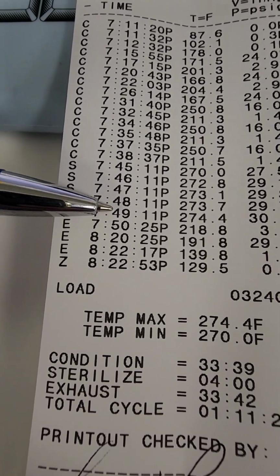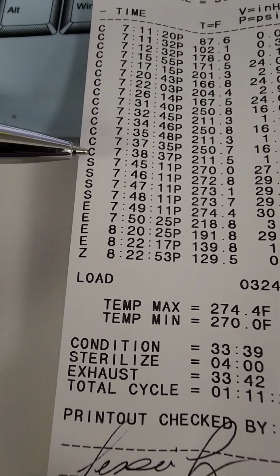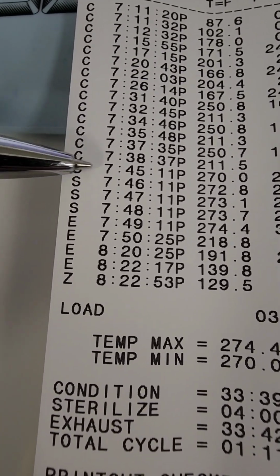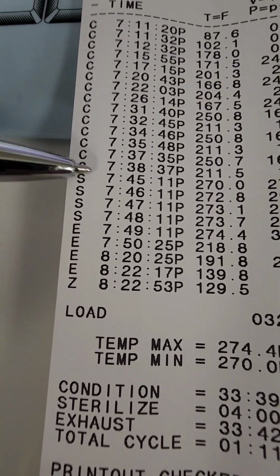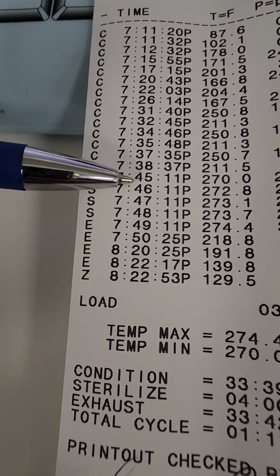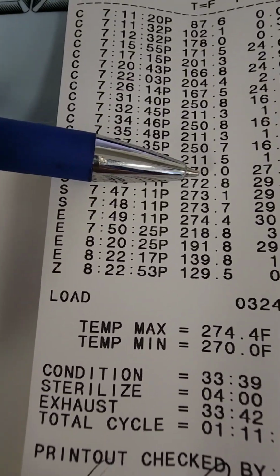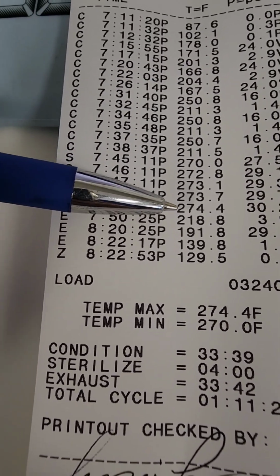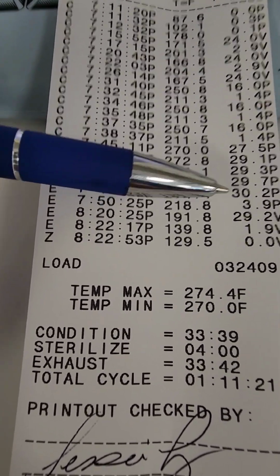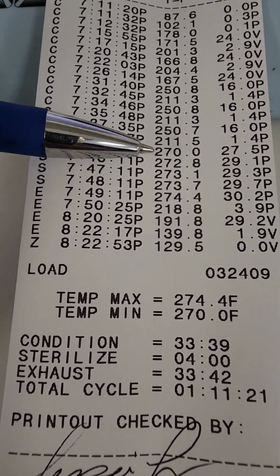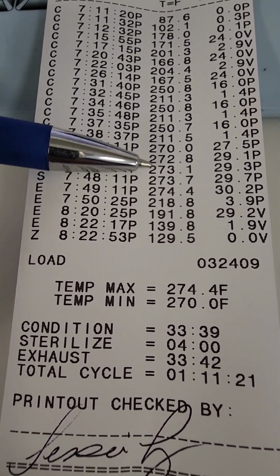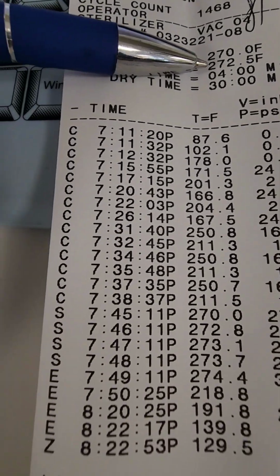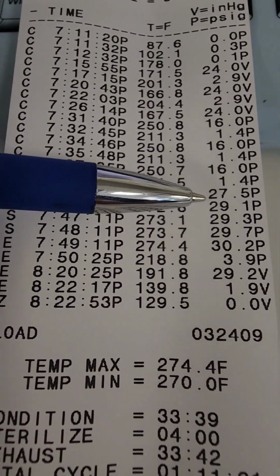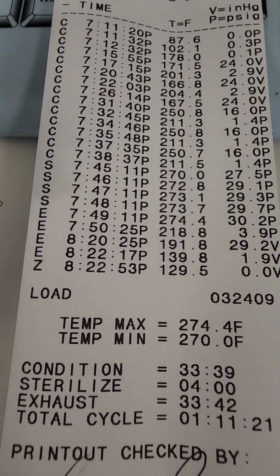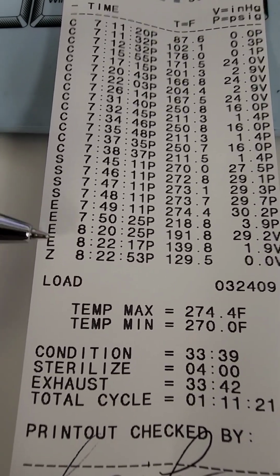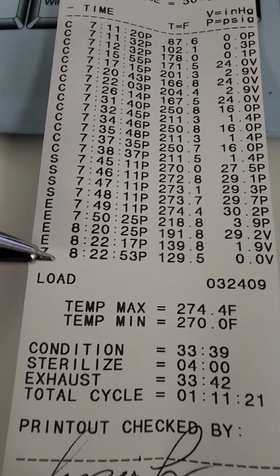So the way you read this is you should have that 4 minute exposure time starting with the first S and ending on the first E. All right. So if you find that first S, that first S is going to tell you that in this example, the first S started at a time of 7:45, and then it ended with an E at 4 minutes after, which is 7:49. My temperature started at 270 and rose all the way up to 274.4, which is higher than the actual control temperature, but that's okay. What you want to look at is that pressure. Was that pressure consistent, or did it jump and fluctuate all over the place? That lets you know a little bit more than the actual temperature.